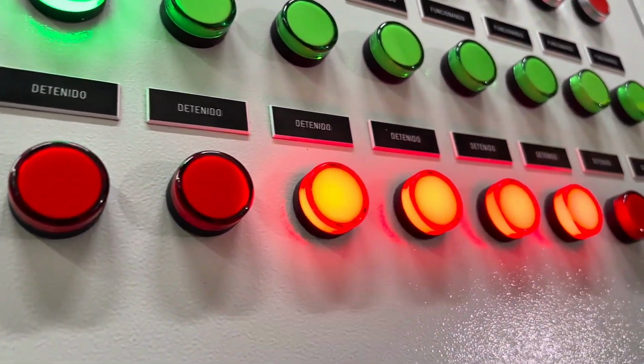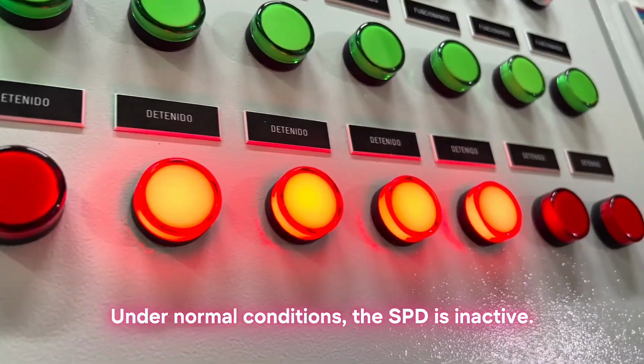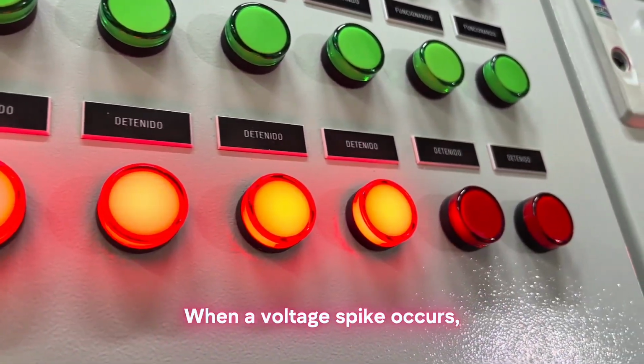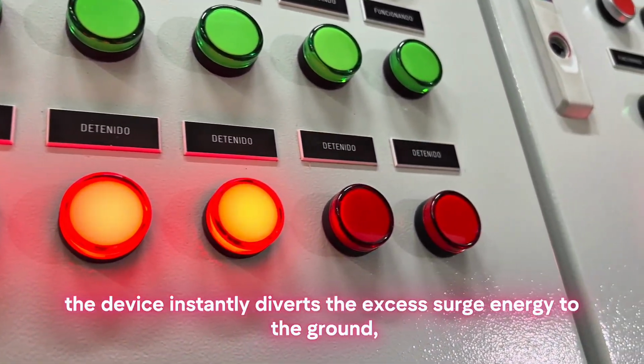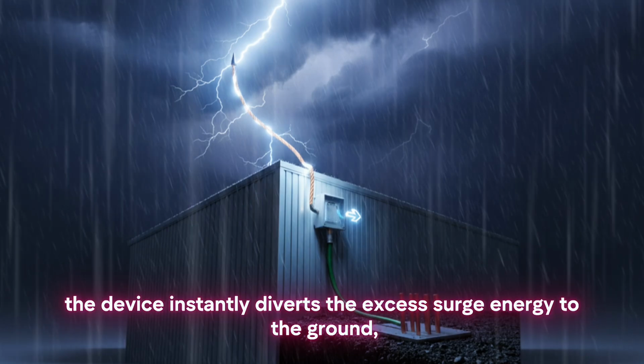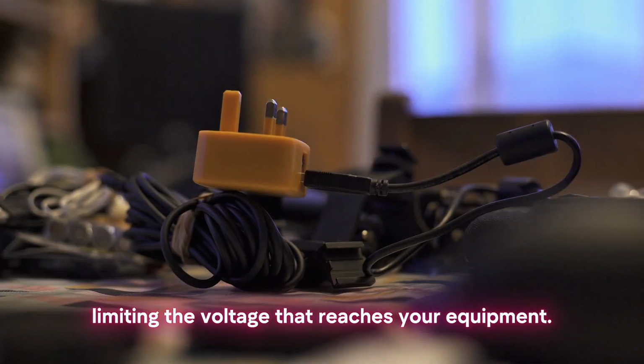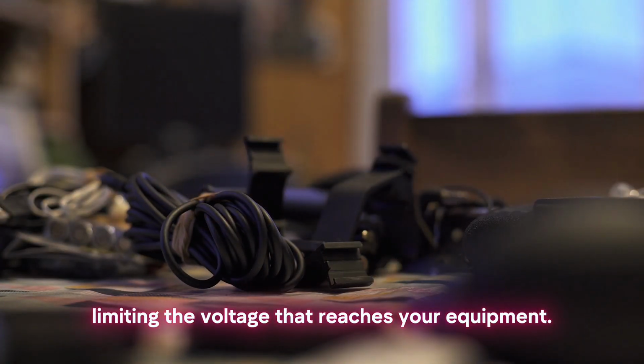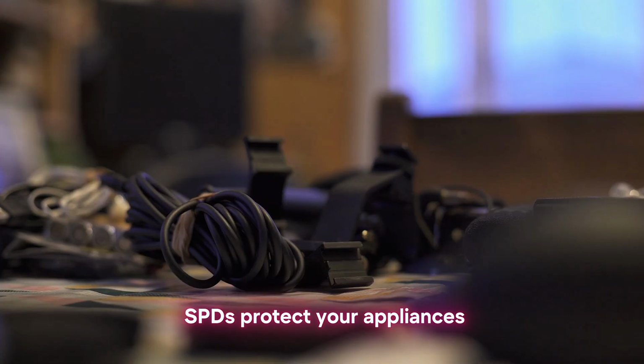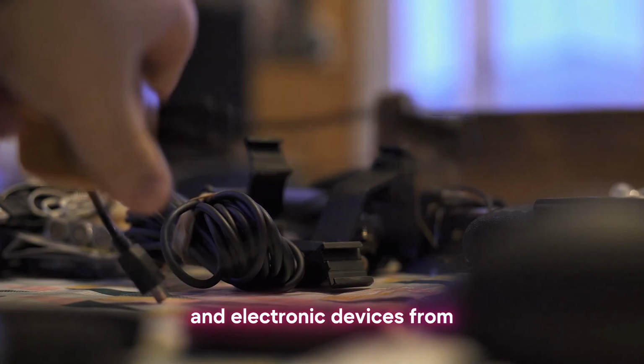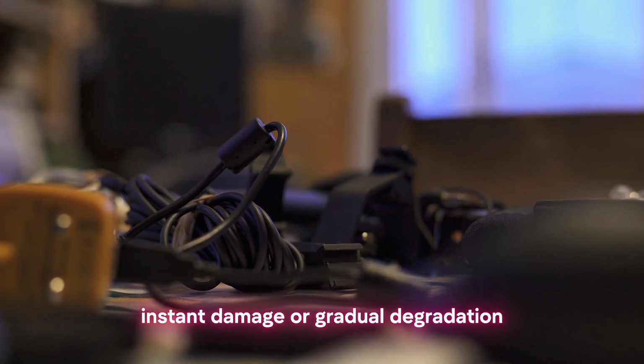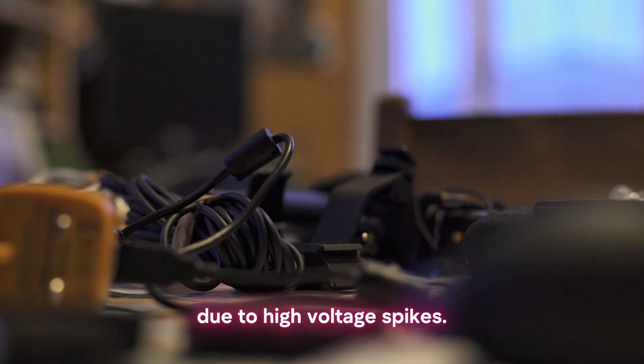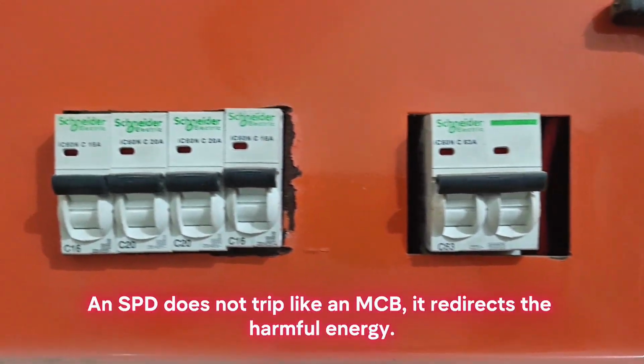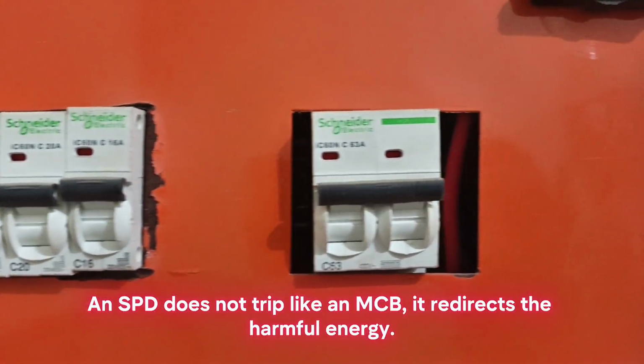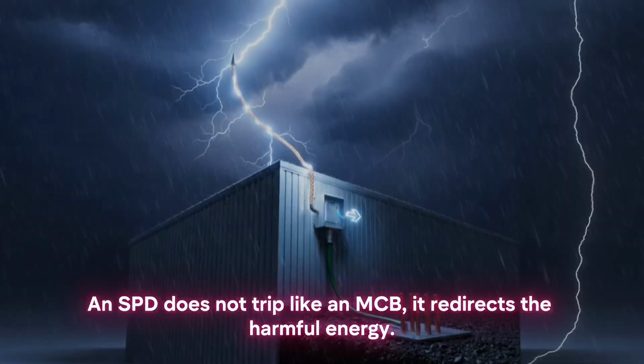How it works? Under normal conditions, the SPD is inactive. When a voltage spike occurs, the device instantly diverts the excess surge energy to the ground, limiting the voltage that reaches your equipment. SPDs protect your appliances and electronic devices from instant damage or gradual degradation due to high voltage spikes. An SPD does not trip like an MCB. It redirects the harmful energy.